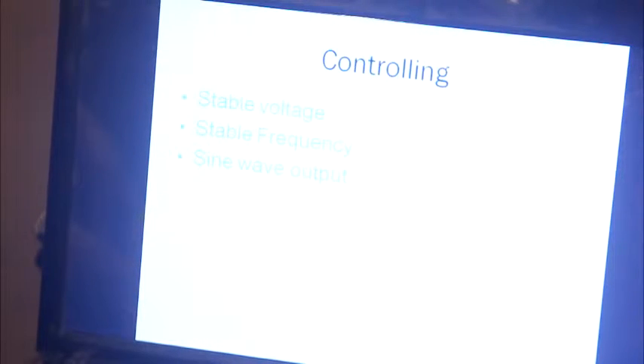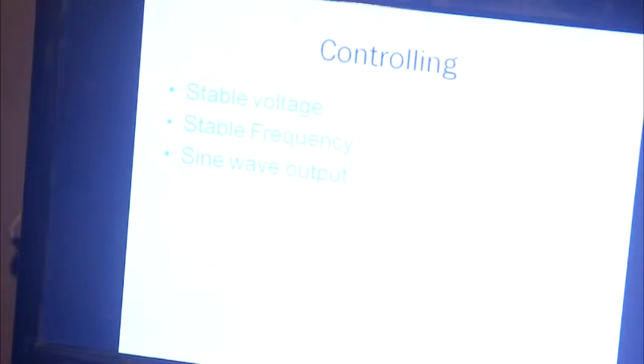What is controlling? There are three main areas to identify whether a system is controlling properly or not: stable voltage, stable frequency, and in AC power, a waveform called sine wave output. If these three parameters are within range, that is a good control hydropower system. In our national grid, voltage is 230 volts, frequency is 50 hertz, and the waveform is a pure sine wave. If we can achieve the same quality in our micro hydropower, that is a very good quality control system.